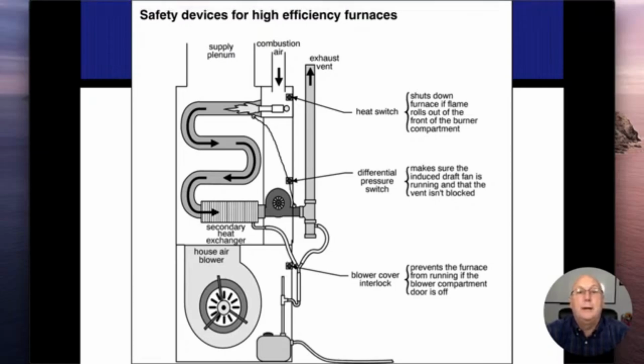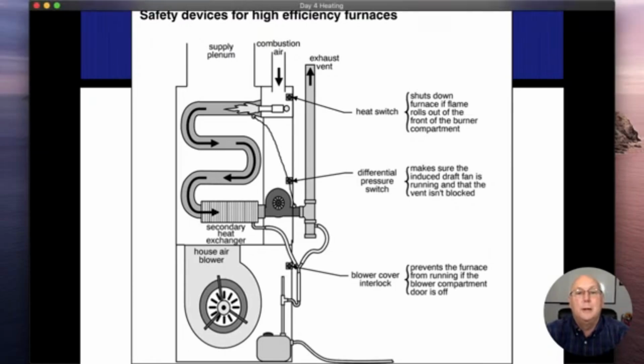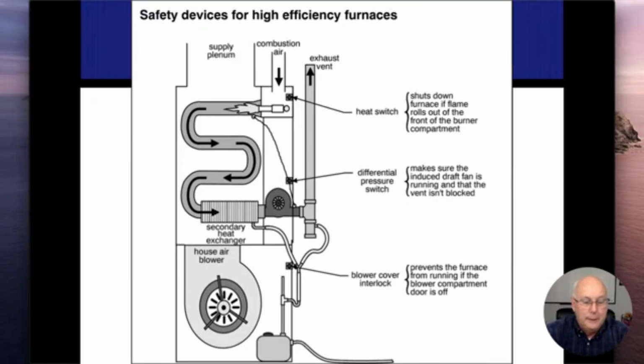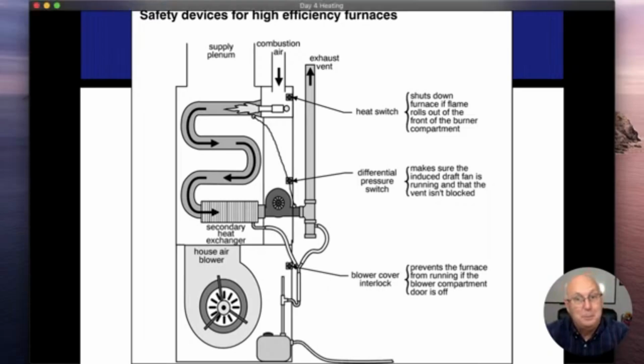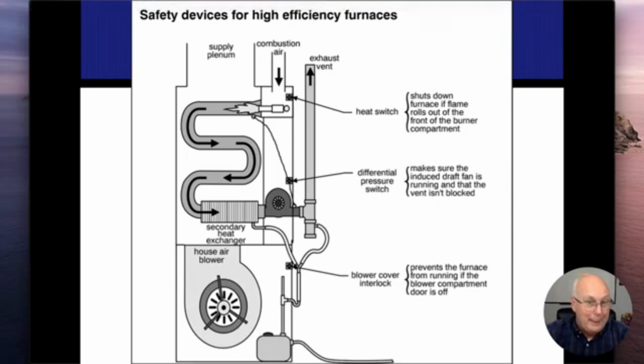Heat switches, so they do have high limit switches on there, pressure differentials we talked about, and then the blower door interlock. Just about every furnace that has a blower fan should have an interlock switch on it. I have seen them bypassed quite often. There's a lot of heating contractors that will just put tape on it to bypass it. That way if the door comes loose, it doesn't shut itself down and people don't get a service call. I get it, and it makes sense. But I am not a fan of bypassing any safety device whatsoever.